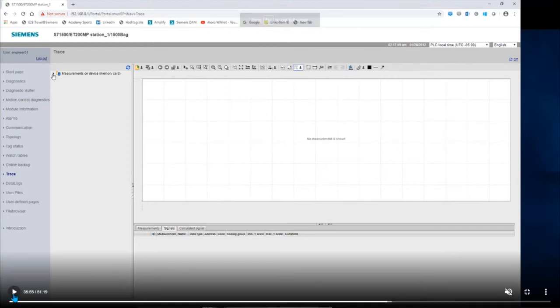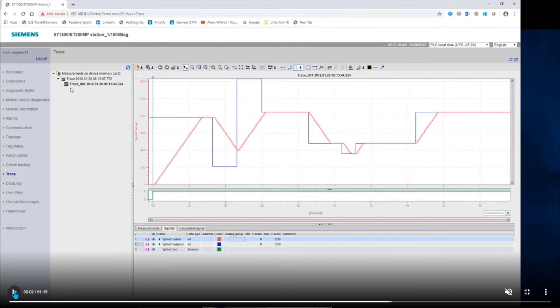So what you're about to see here, more or less, is a video that's going to show how you can access the trace through the web server. The traces are always set up prior to, meaning that you have to configure what you're going to be tracing, and then you would have to upload that trace to the PLC to make it accessible from the web server or from the screen itself.